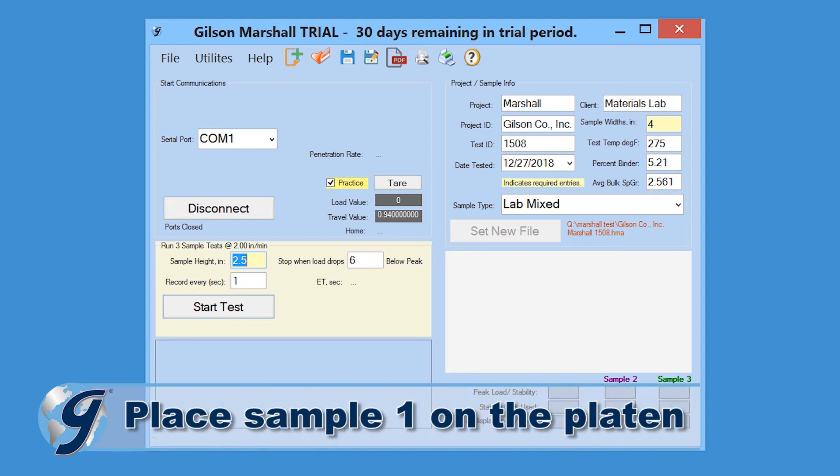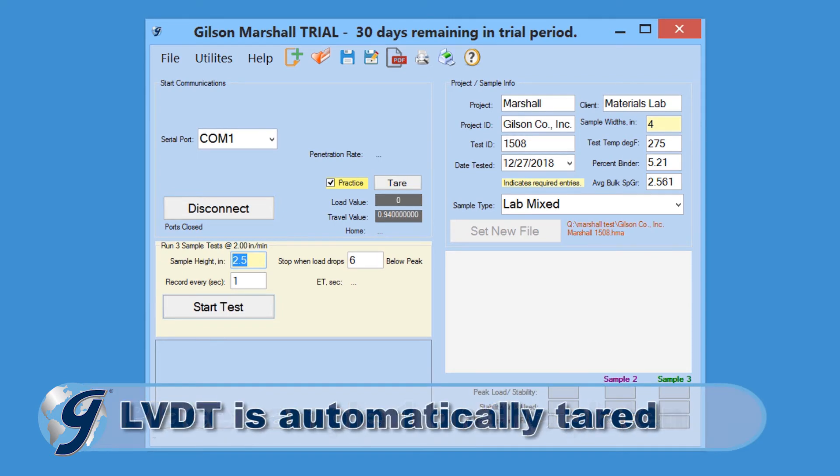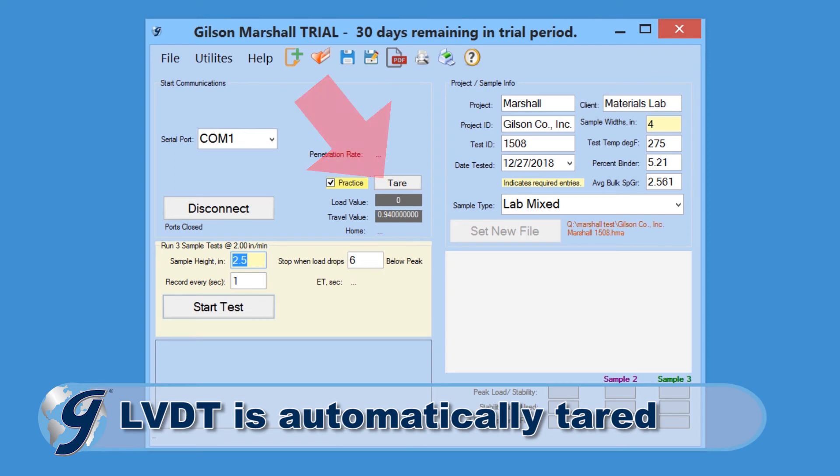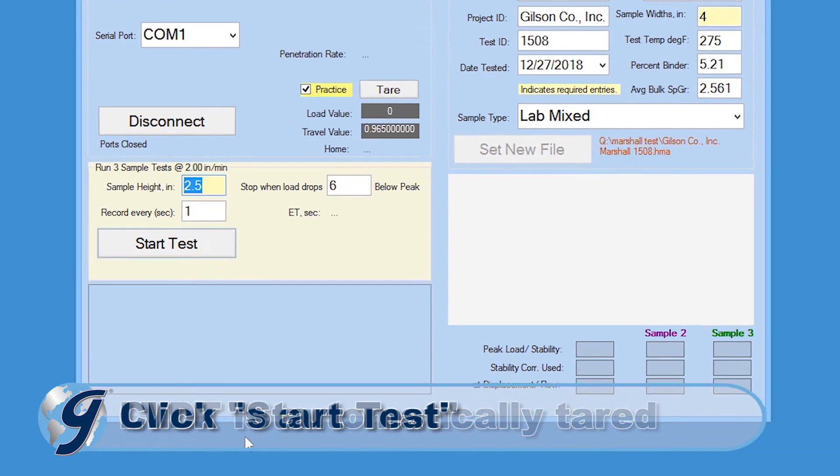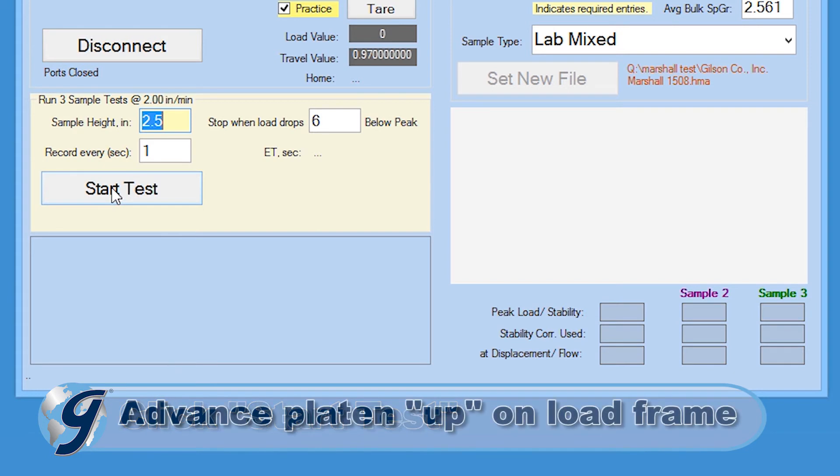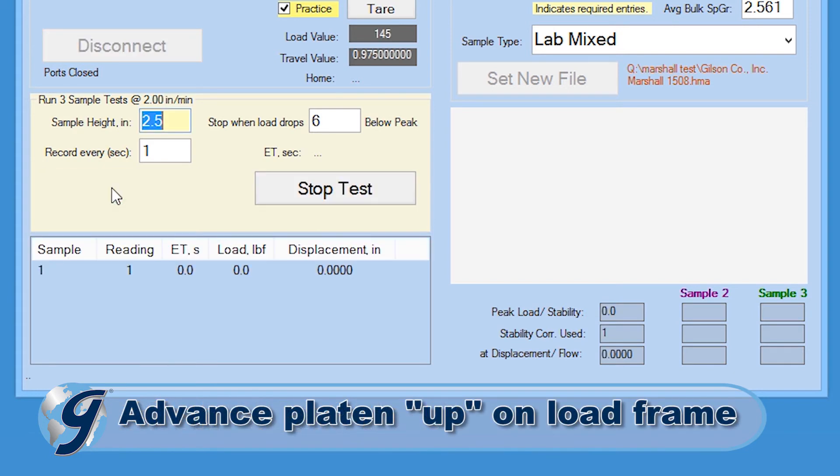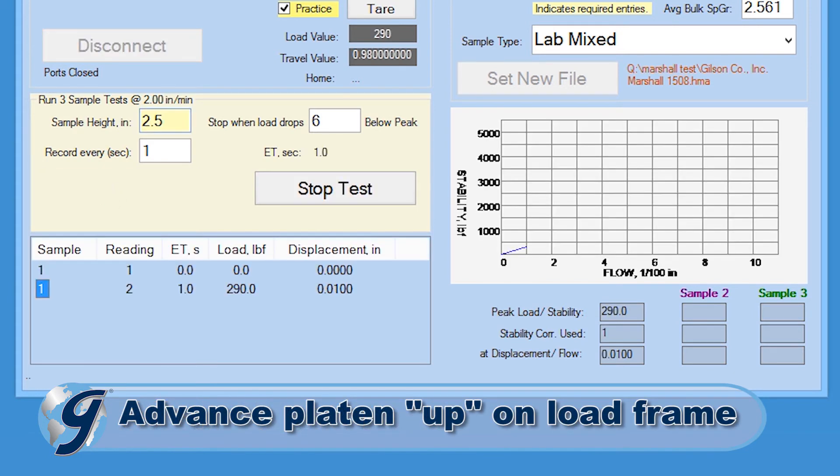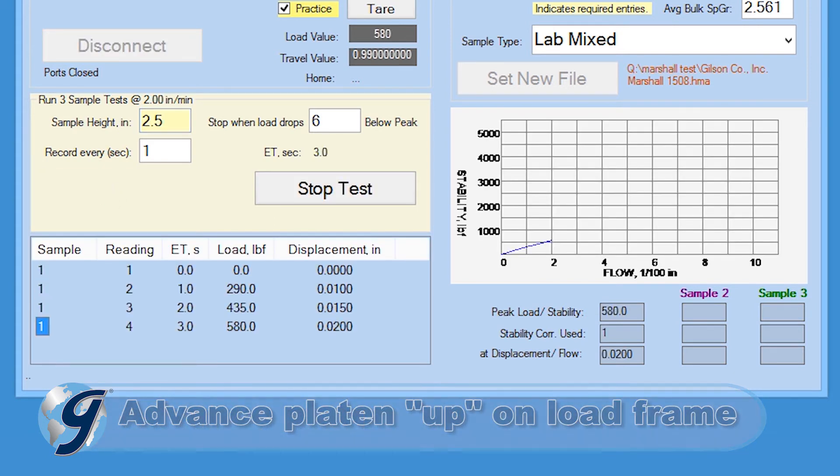Now you are ready to begin the test. Mount the first sample on the platen. It is not necessary to click tare. The displacement transducer will automatically be tared at the beginning of the test. Click start test, switch the platen advance to up, and the program will begin recording data.